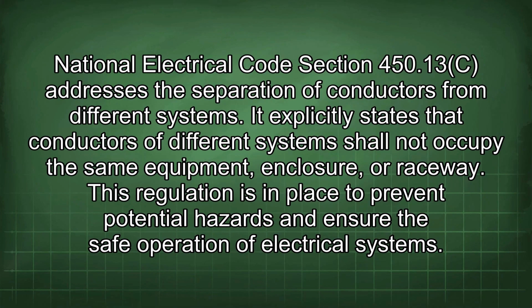National Electrical Code Section 450.13c addresses the separation of conductors from different systems. It explicitly states that conductors of different systems shall not occupy the same equipment, enclosure, or raceway. This regulation is in place to prevent potential hazards and ensure the safe operation of electrical systems.